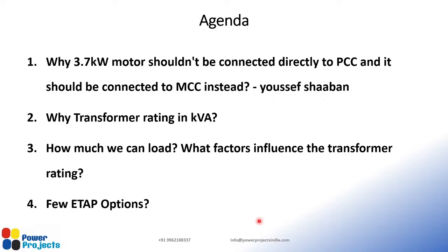All right. So is there any other questions? It means there would not be any coordination when an MCCB is used as an incomer. How can this be taken care of? I'm not saying that you don't need coordination when an MCCB is there. Still you need to coordinate, but that's where the difference comes. When you have current limiting breakers and non-current limiting breakers, you can just google current limiting circuit breakers. Nowadays most molded case circuit breakers are of the current limiting type, and they curtail this current much before it reaches its peak.